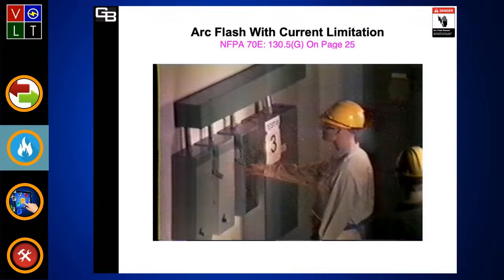Have we reduced that? A lot of you out there know if you're using fuses as a current limiting device, you go to 240.67 in the NEC. If you're using a circuit breaker with an energy reducing type reduction, you go to 240.87. Keep that in mind, you can see how you could use fuses or circuit breakers to perform this task. Let's go to the next one.